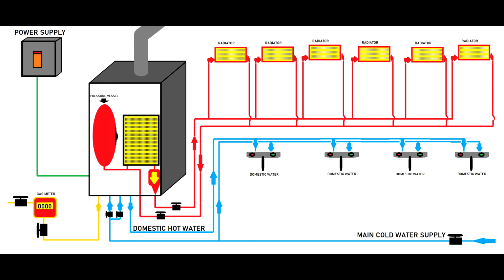The ball painted in red is the pressure vessel. If the installation is incorrectly calculated, that pressure vessel is supposed to take the extra volume generated by the water heating process. Now if the vessel is too small, which is not right, because when you choose the boiler it will have a standard pressure vessel, it is bad. But if the volume of the water you want to heat is big, you have too many radiators, you might need a secondary pressure vessel just to control the system's elasticity. And this can happen because of another reason. If you have a very badly contaminated heat exchanger and the water is not circulating very fast, you might have boiling water inside your heat exchanger, and then the pressure in the system will rise considerably.